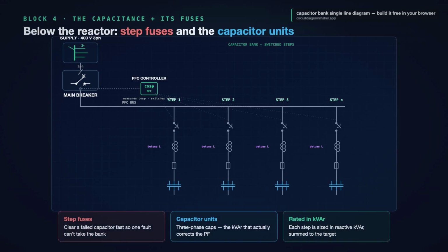Block 4. The step fuses and the capacitor units themselves. Under the reactor, each phase of the step gets a fuse. If a single capacitor fails, and capacitors do fail short, the fuse clears that one fast, so one bad cap cannot take down the whole bank or feed a fault.